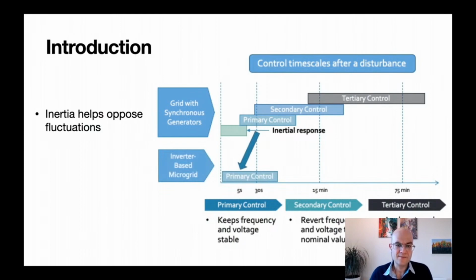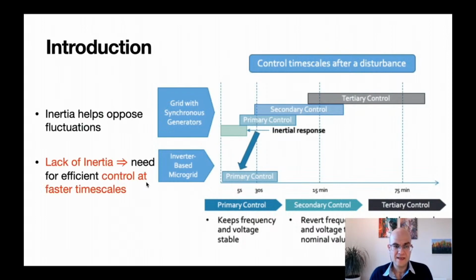Now, in an inverter-based grid, this inertia of the generators is not present, and therefore this response at the very fast timescale, this timescale of milliseconds, is implemented by the control policies of the inverters. This is in general a highly non-trivial control problem due to the fast timescales involved and also the potential interaction between the different converters.